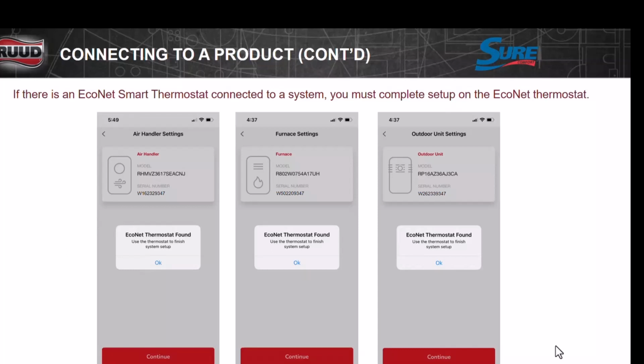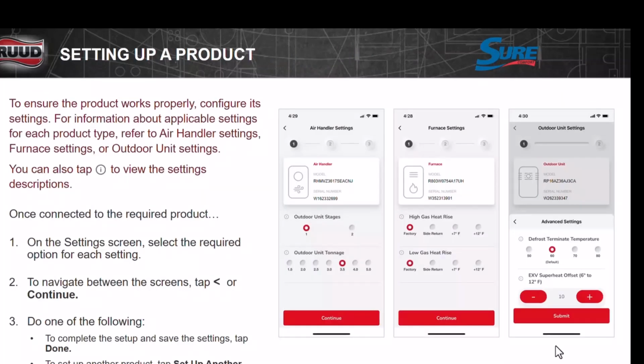Now, if you have an EcoNet thermostat connected to it, you're going to get a message saying that it found an EcoNet stat, and you need to finish the setup in that stat. When you get in to set the thermostat up, if it's not an EcoNet thermostat, then you can go in and set stages, things like the tonnage. You can go change things like the heat rise on your gas furnace.